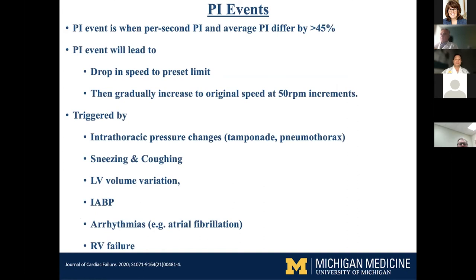A PI event will lead to a drop in speed to the preset limit, and then the pump gradually increases back to the original speed at 50 RPM increments. PI events can be triggered by relatively benign things like sneezing or coughing or intrathoracic pressure changes, or by more significant issues like pneumothorax, tamponade, LV volume variation, presence of an intra-aortic balloon pump — where balloon deflation suddenly increases afterload — any arrhythmias, or the occurrence of RV failure.